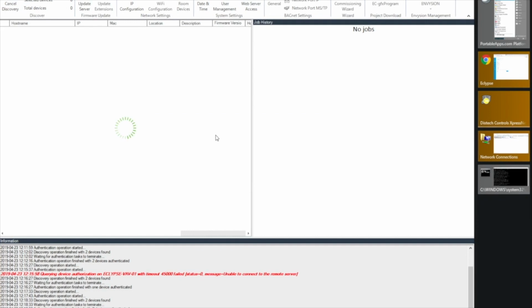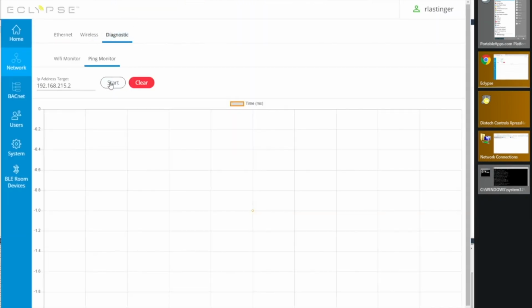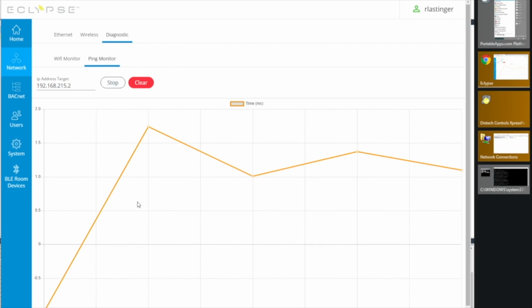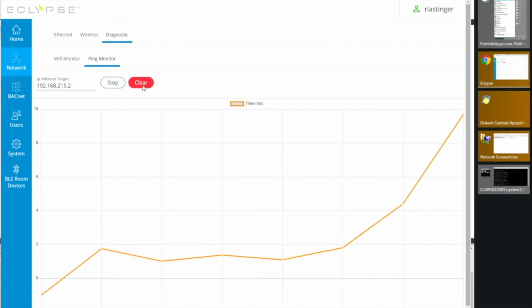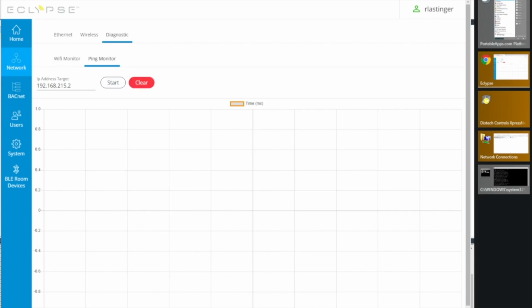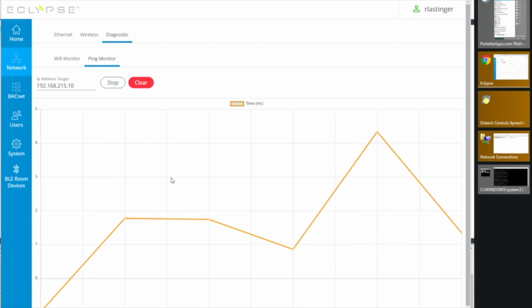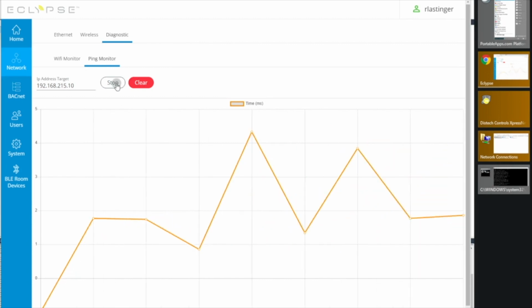If you have 300 controllers, and you want them on a single subnet, then you should use the calculator and put 300 hosts in there and figure out what an appropriate subnet would be for 300 controllers. Also, if you have 6 controllers, you might leave yourself a little breathing room and say, okay, I'll have a subnet with 30 or a subnet with 14, but it doesn't make sense to have a subnet of 255.255.0.0 with thousands of potential addresses for 7 controllers, right?